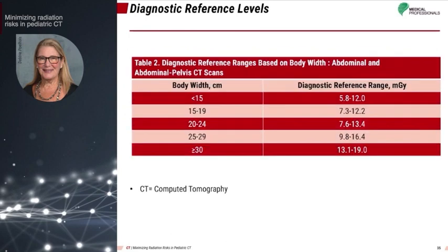The Diagnostic Reference Range, or DRR, is a quality improvement tool that provides an estimated minimum radiation dose to the patient, below which reduced image quality may not reach diagnostic quality, and a higher estimated patient dose, above which the dose may be too high.